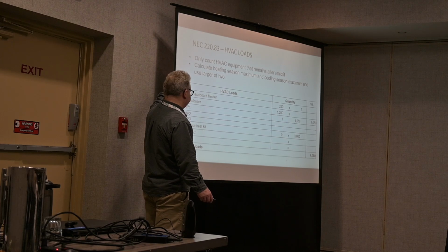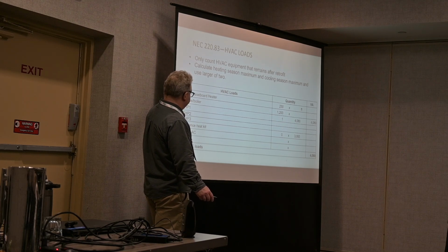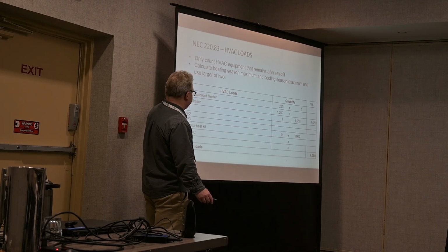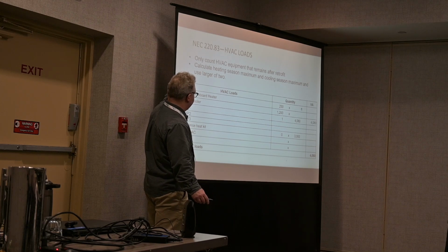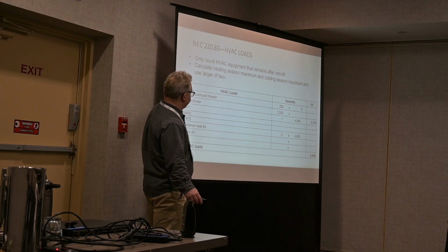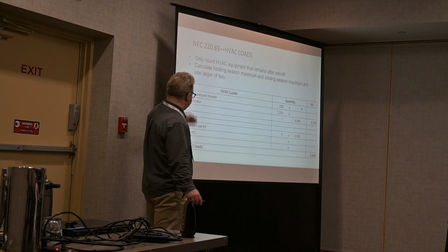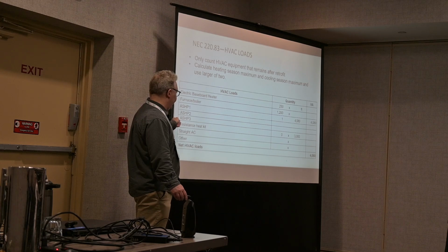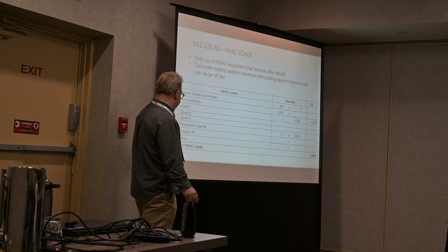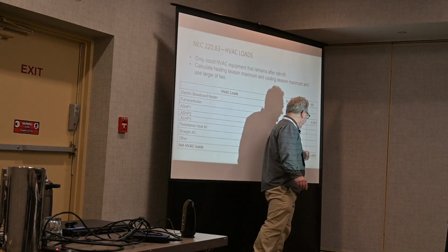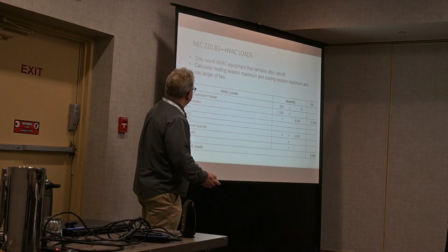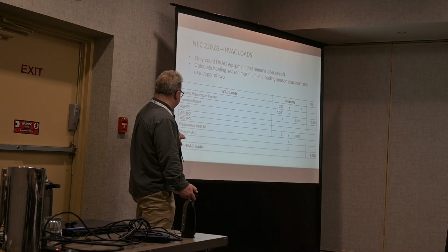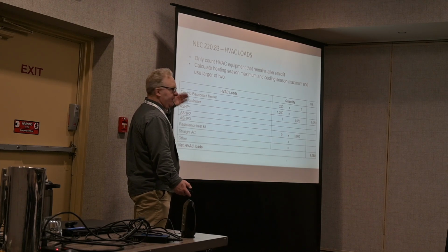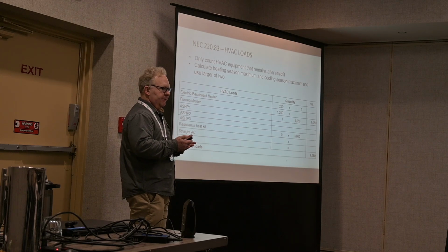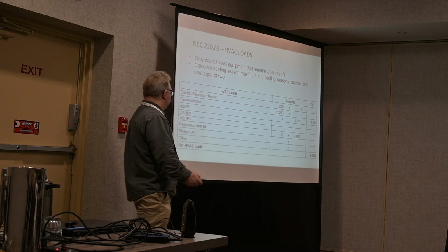Now, we're down in the HVAC section of this worksheet. And I didn't have any electric baseboard. The furnace that was there is going away, so I don't have to count it in this spreadsheet. I've got my heat pump. I'm not putting in a resistance heat kit. If I did, I'd have to put it in at whatever its rated value is. And this gives us the total amount of HVAC loads that I'm going to be adding to this system. If we had a straight air conditioner and electric baseboard, for example, we might have different numbers for heating and cooling, and we just have to pick the larger of those two.